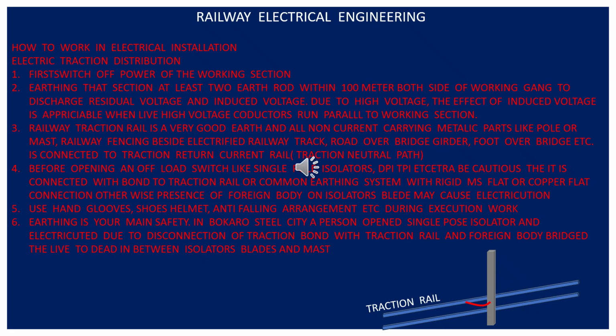So what we are doing, we are making a connection, shown in red color, from the mast to the railway track. It is called the bond, the structure bond. It plays a very important role for our safety. Suppose any insulator has broken, it will immediately touch the mast and 25 kV will energize the mast, but it will not affect you. If you touch the mast, the current will not pass through your body because of the low resistive path through this bond. It will return to the substation and the circuit breaker will trip immediately through the relay. It is an earth fault. So our safety mainly depends on this structure bond.